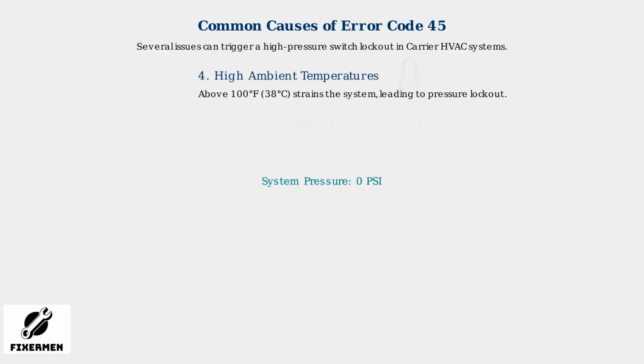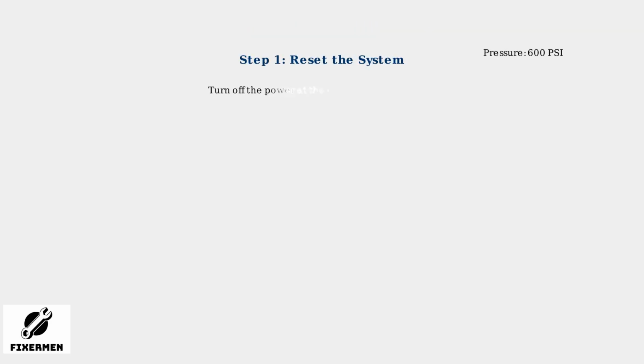The fourth cause is high ambient temperatures exceeding 100 degrees Fahrenheit or 38 degrees Celsius. In extreme heat, the system struggles to dissipate heat effectively. This puts enormous strain on components, causing pressure to spike and triggering the safety lockout. Addressing these underlying causes through proper maintenance and timely repairs is crucial for preventing repeated high-pressure switch lockouts in your HVAC system.